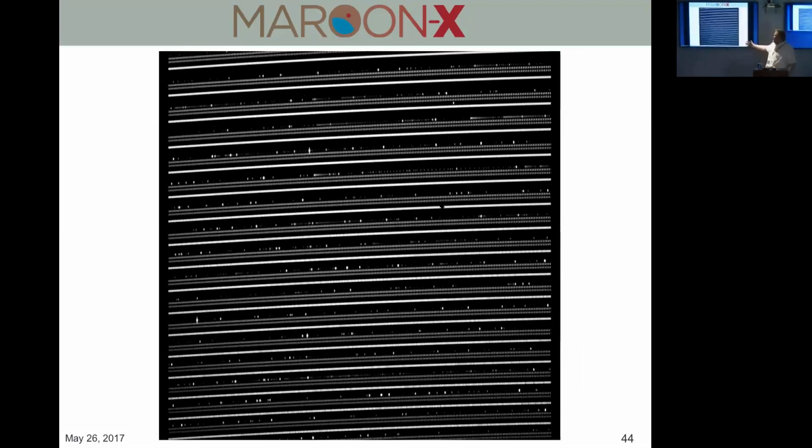So this is how this looks for the full frame. You see roughly how your Thorium-Argon looks in comparison to the etalon. And again, logarithmic scale. So we have already tried to maximize the Thorium-Argon coverage, but you see at that point even the first argon lines are starting to bleed. So this is one of the big problems if you use Thorium-Argon for simultaneous calibration, that your brightest argon lines are bleeding into your science spectrum. And so HARPS, for example, stopped at some point doing the simultaneous calibration and basically relies on taking a spectrum before and after each science observation, which is not very good for instrumental efficiency.